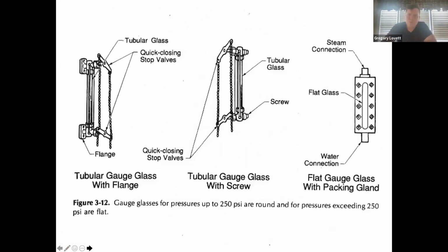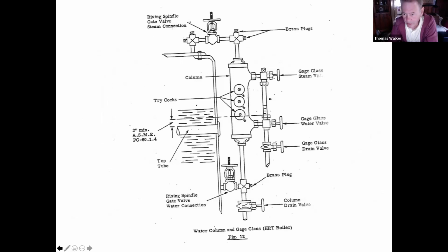What would be an example of a secondary low water cutout if the primary's in the water column? Well, the second one could be on the opposite side of the boiler on a second water column. That's pretty common. It could be a different type. Remember, we talked about the probe type. Requiring a manual reset. So they got all kinds of combinations the way they do it. But once they train you on a particular boiler, they'll explain to you what you got.